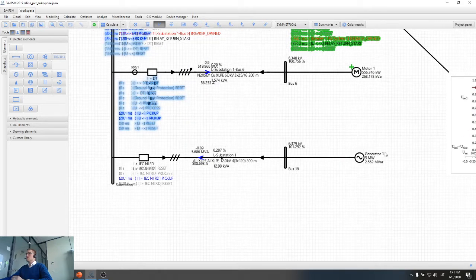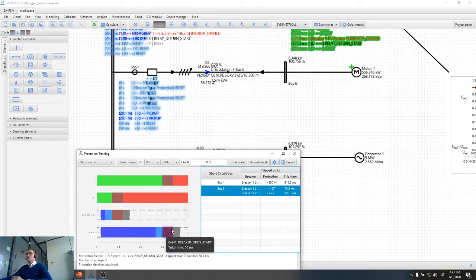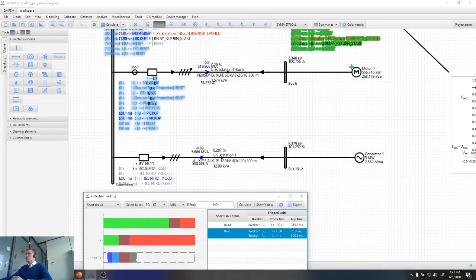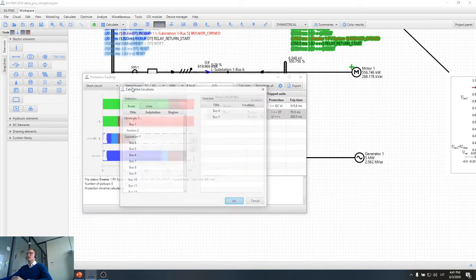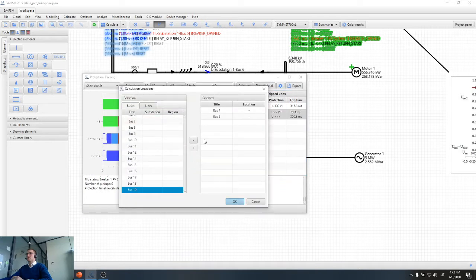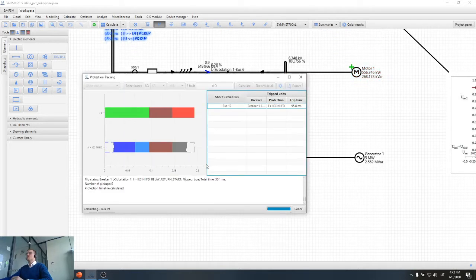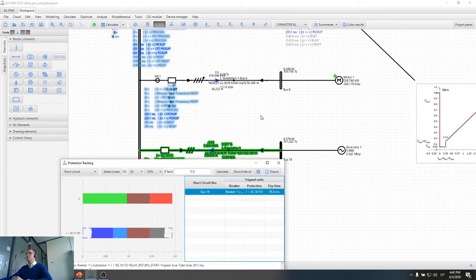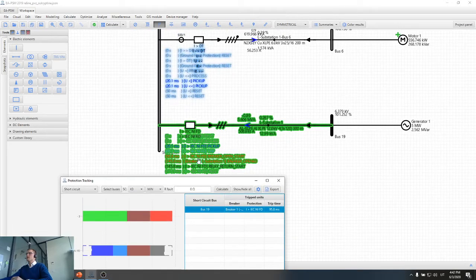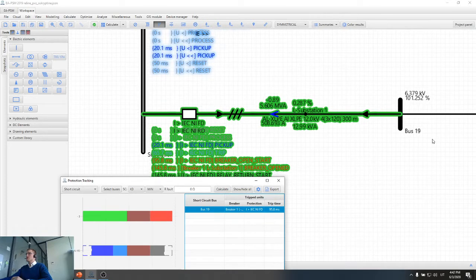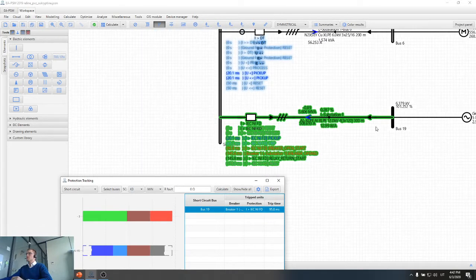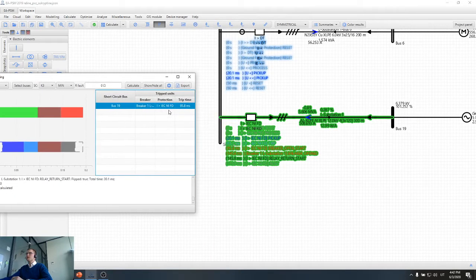Also, we can simulate generator protection operation. So the generator is connected to bus 19. So from the list here, we can select bus 19 as well. This I will disconnect. So in case of bus 19, what has tripped is basically the relay here. It disconnected the bus 19 from the rest of the network. And I can see that the generator is protected by the directional protection devices, and the forward direction protection device has tripped.